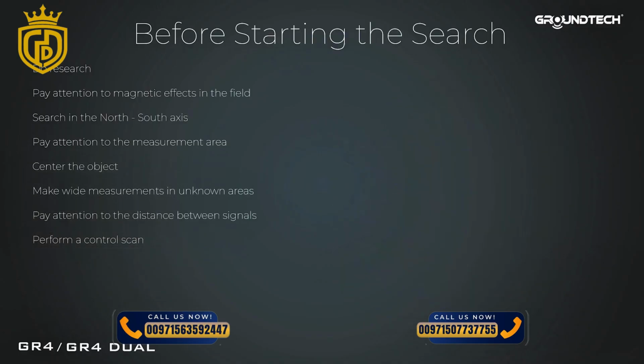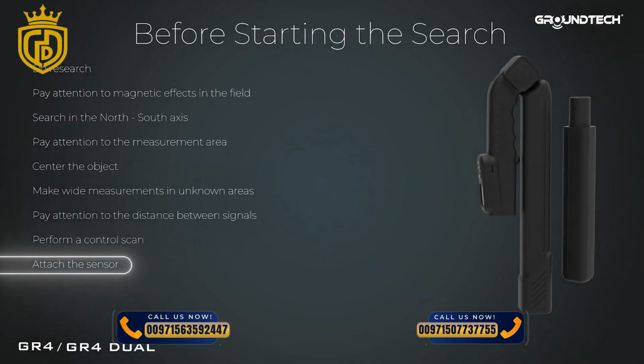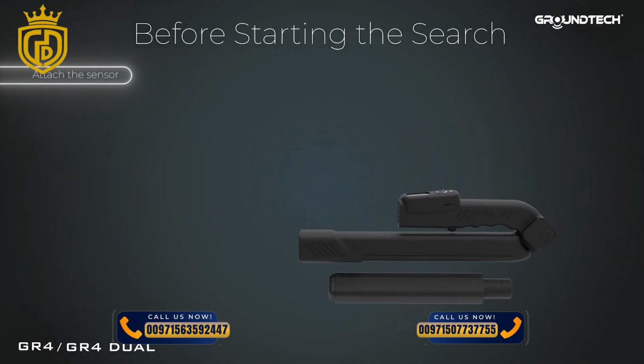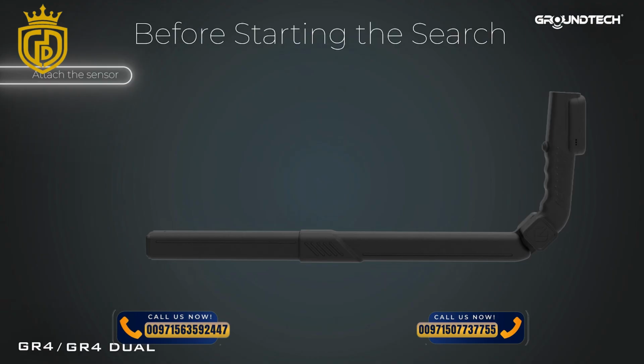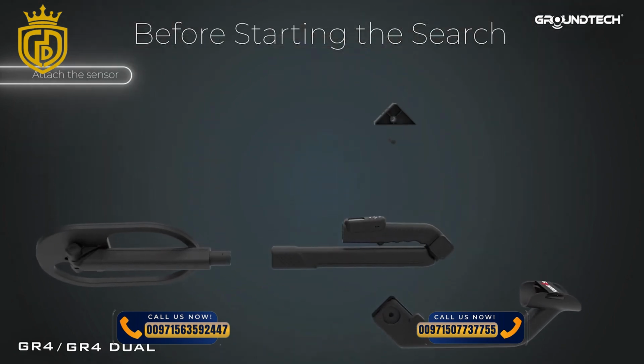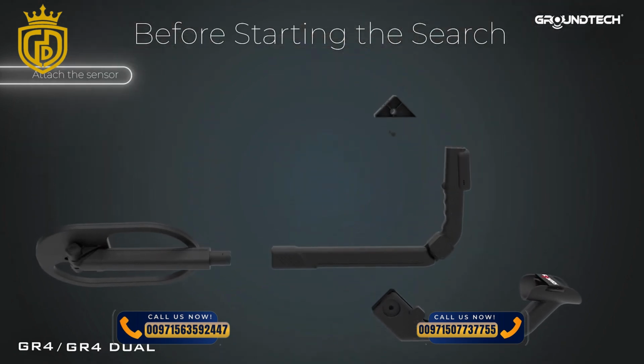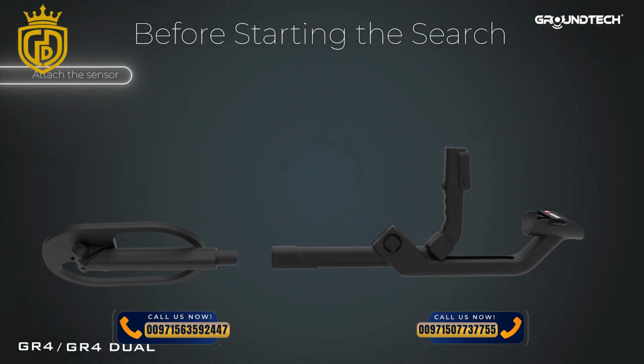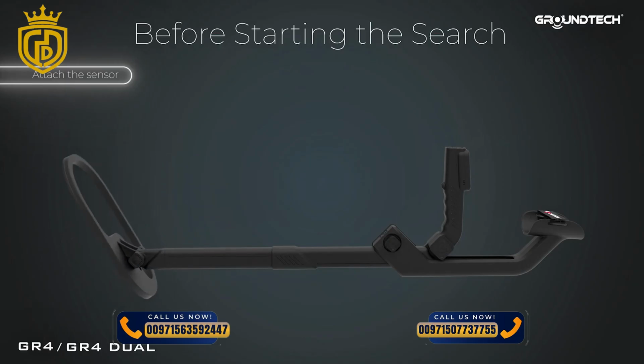Thanks to its modular structure, the sensor of GR4 is attachable and detachable. Before using the device, make sure that the sensor is correctly placed by attaching it to the main device and turning it gently to stabilize it. With GR4 Dual, it is necessary to mount the armrest as well as the detector head. You can stabilize the detector head by attaching it with respect to the requisite angle and by rotating it. As for the ergonomic armrest, you can easily set it by aligning the holes with the screws as shown in the video.